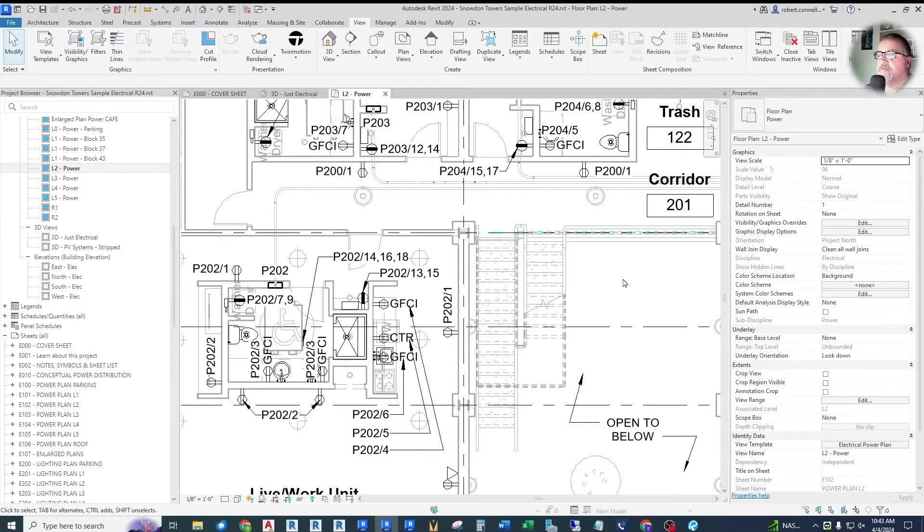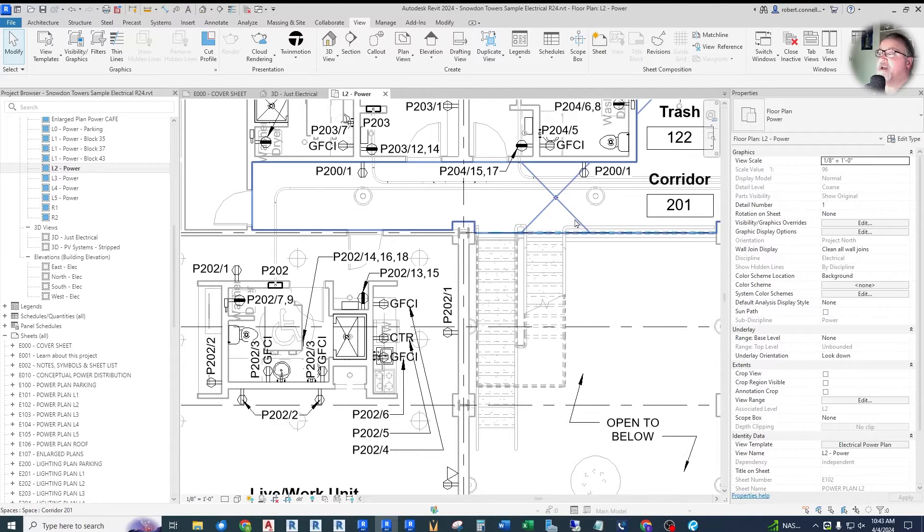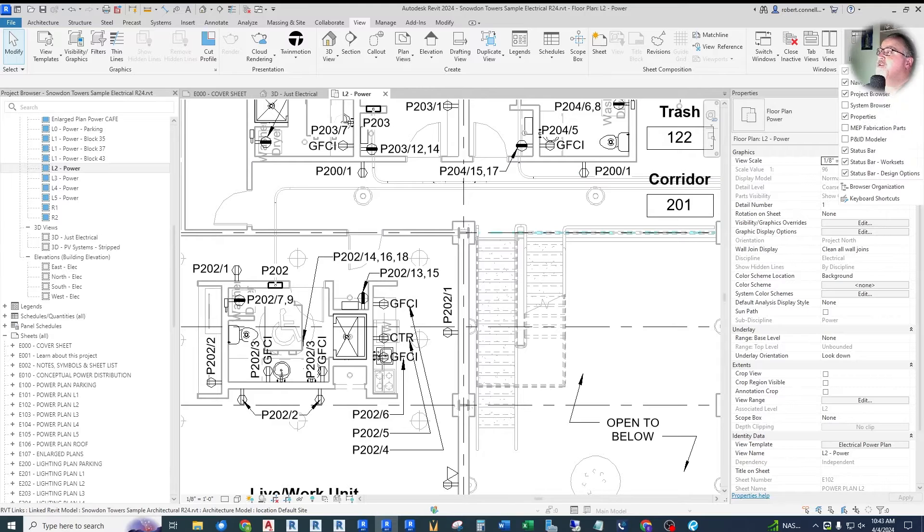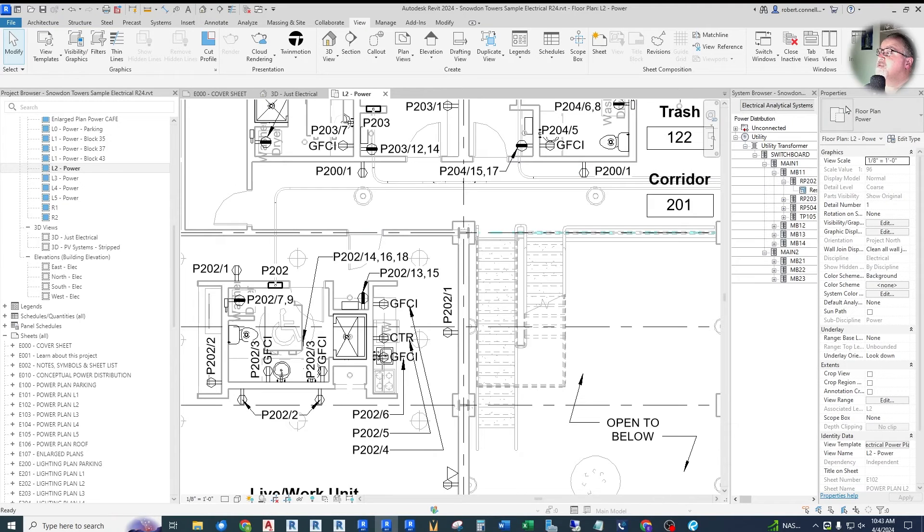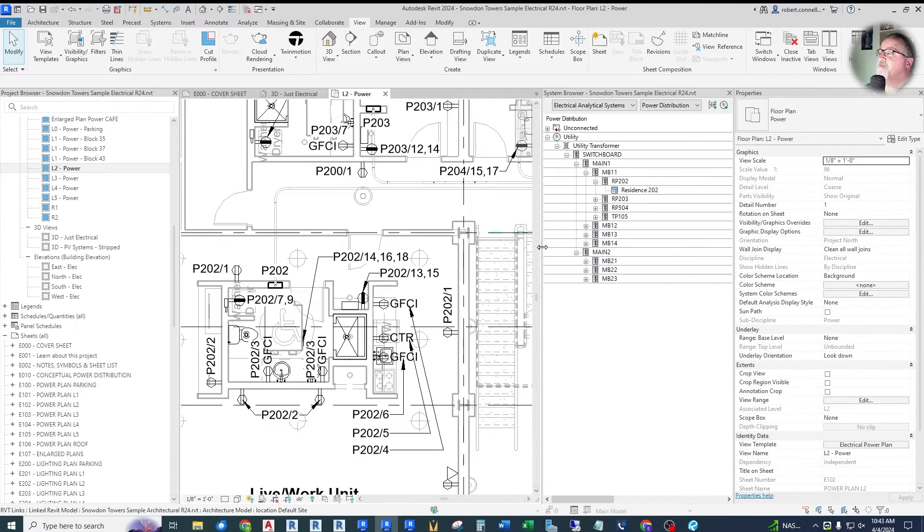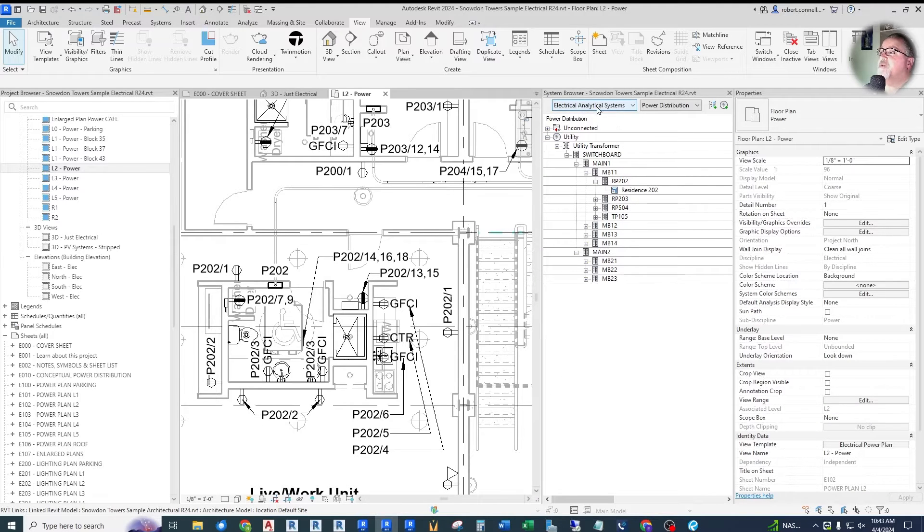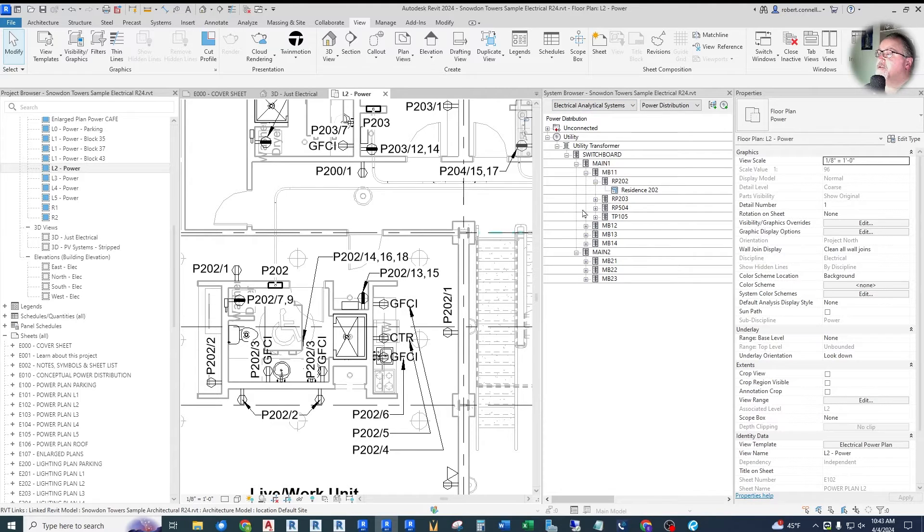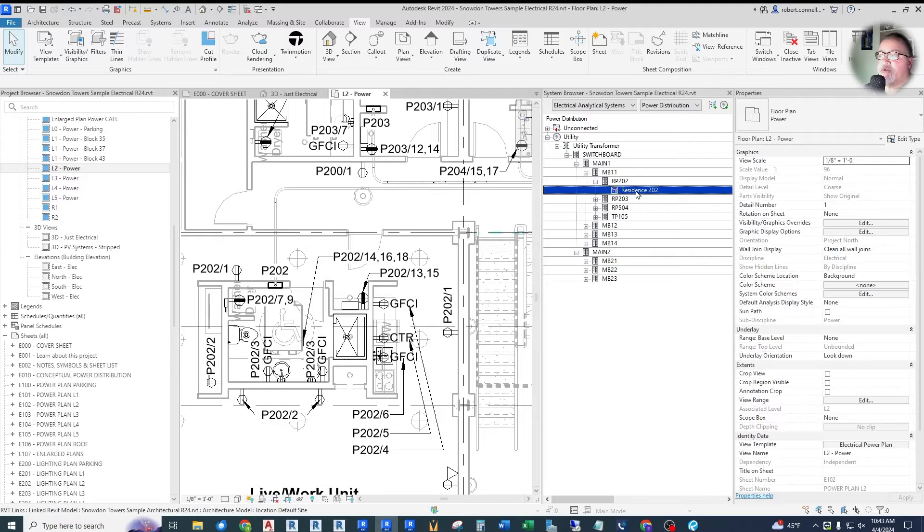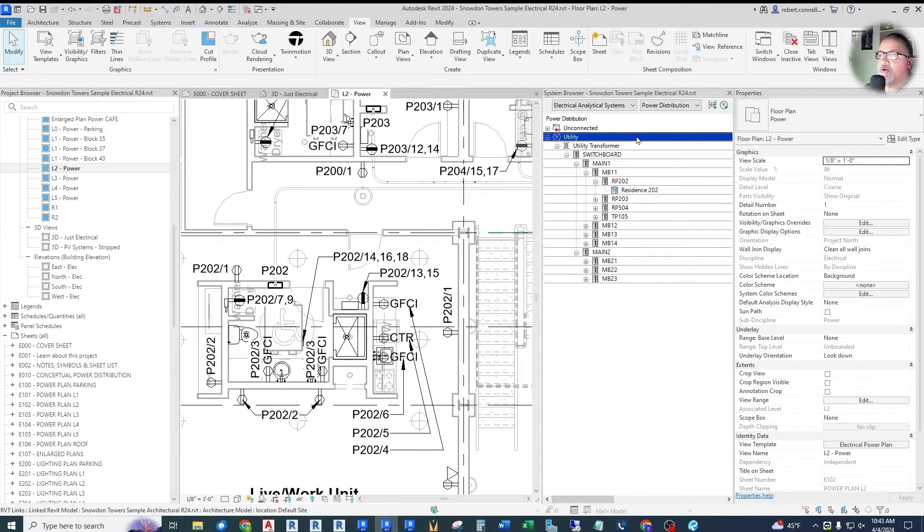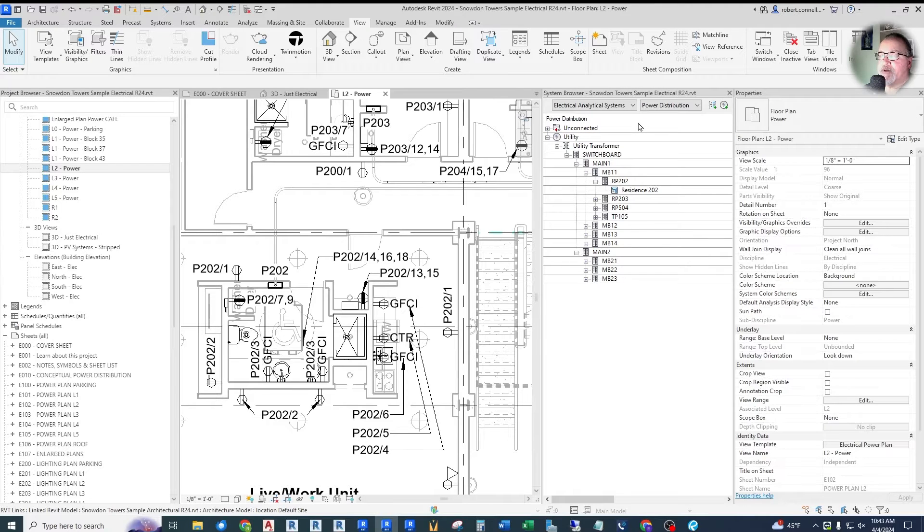They've made a few changes and updates to the electrical analysis properties within Revit 2025. So for example, here in Revit 2024, if you go up to the user interface, click the system browser and expand this out, this system they added in 2023, where you can have an electrical analytical system, where you can just have loads and equipment represented as square footage values or actual amp values, actual VA values, it would only handle three phase loads.